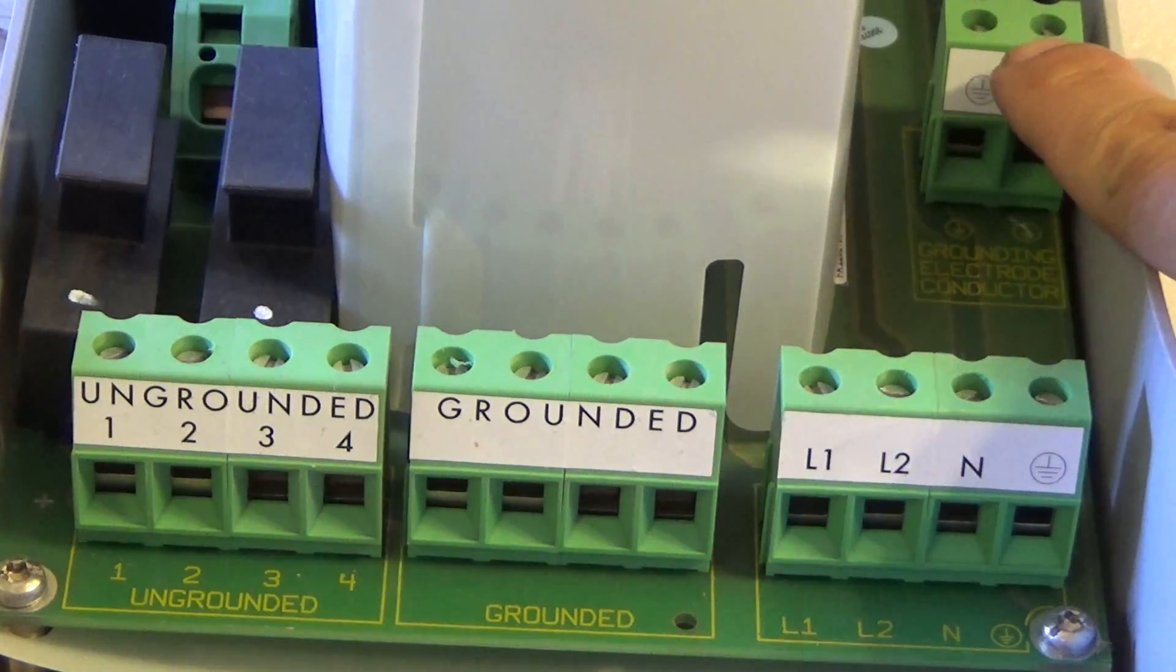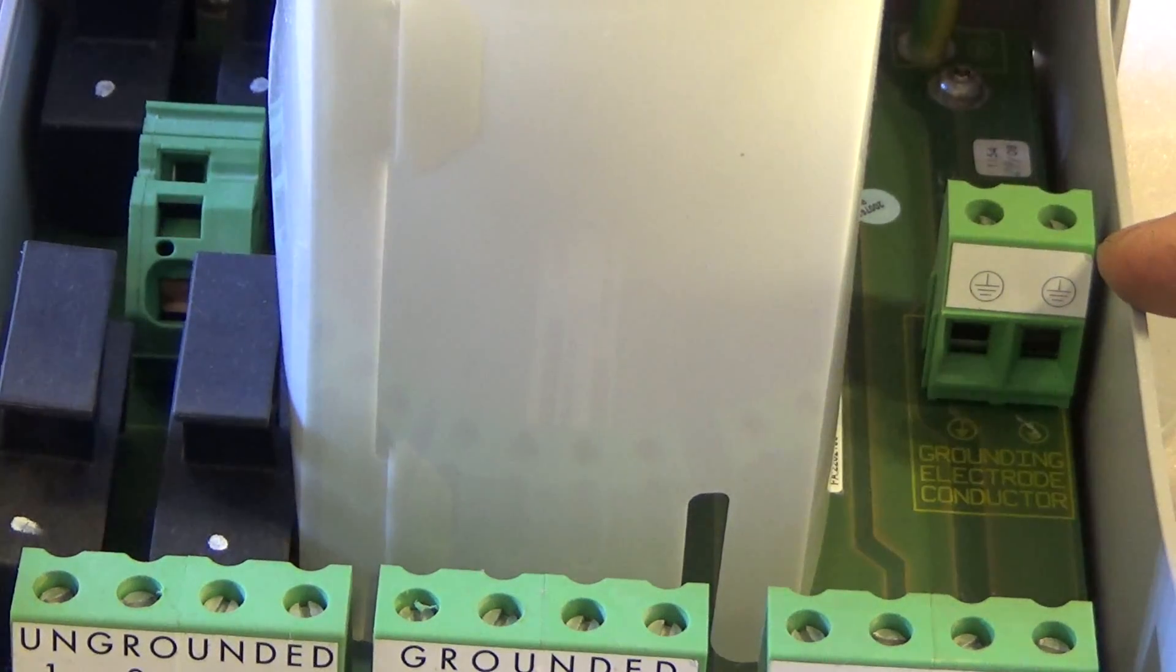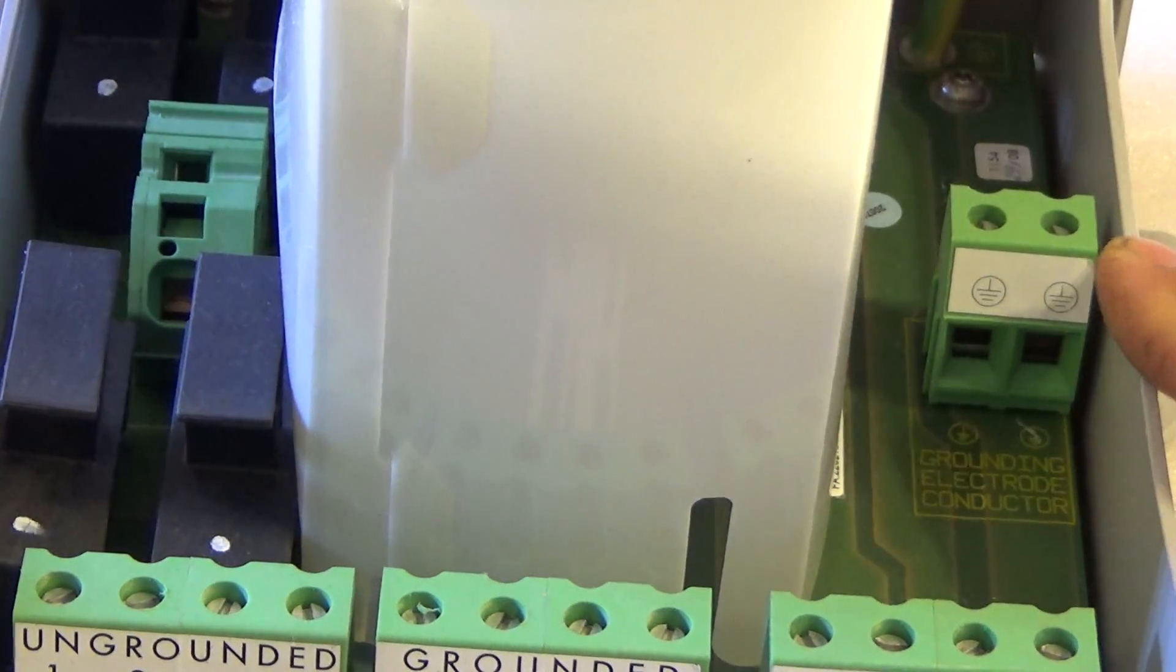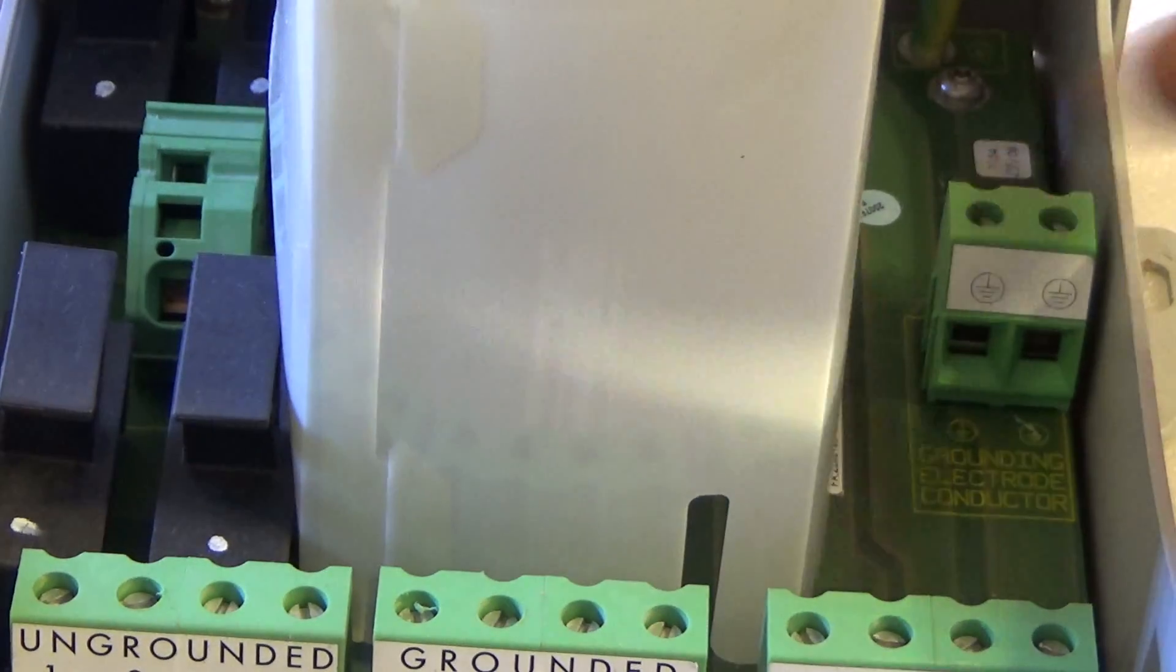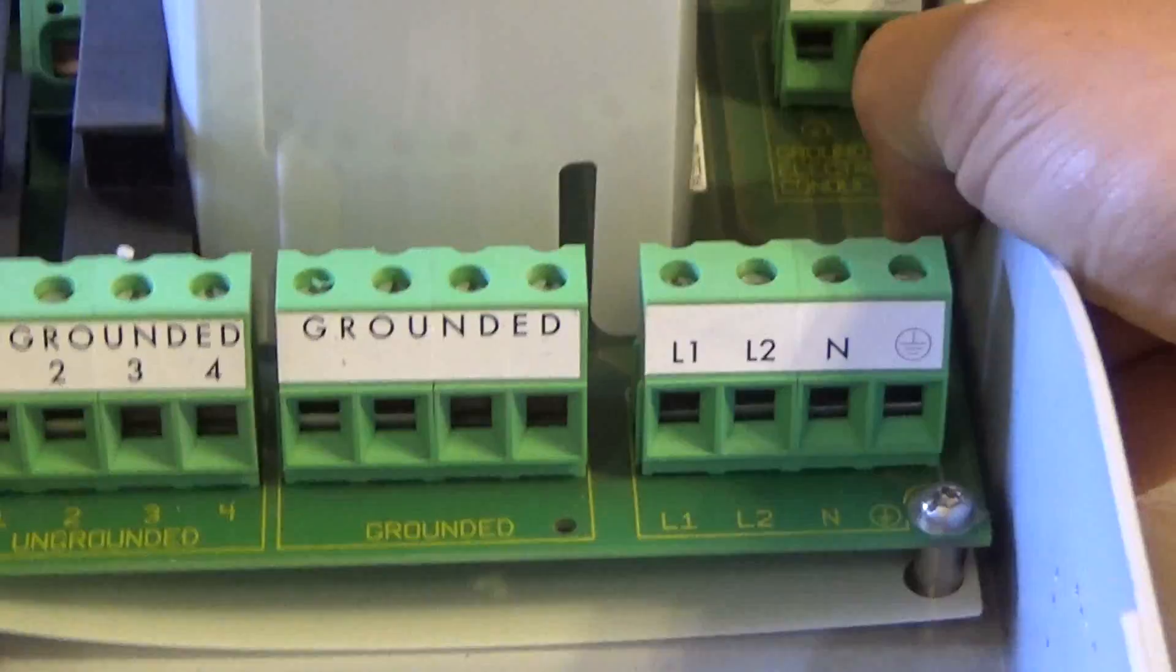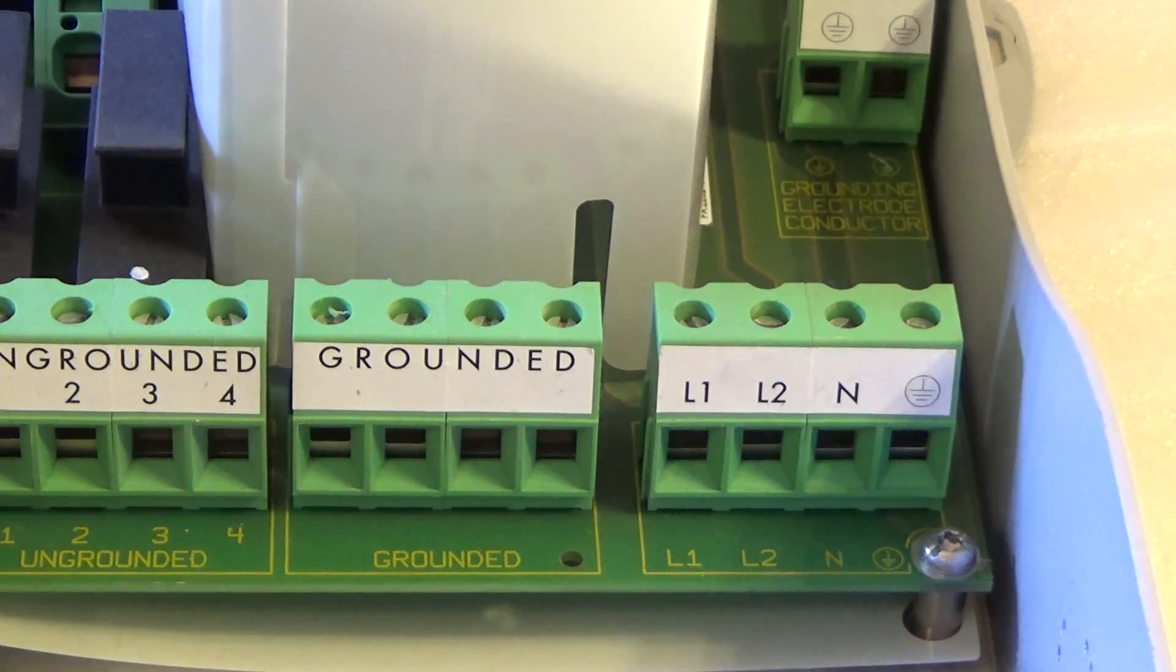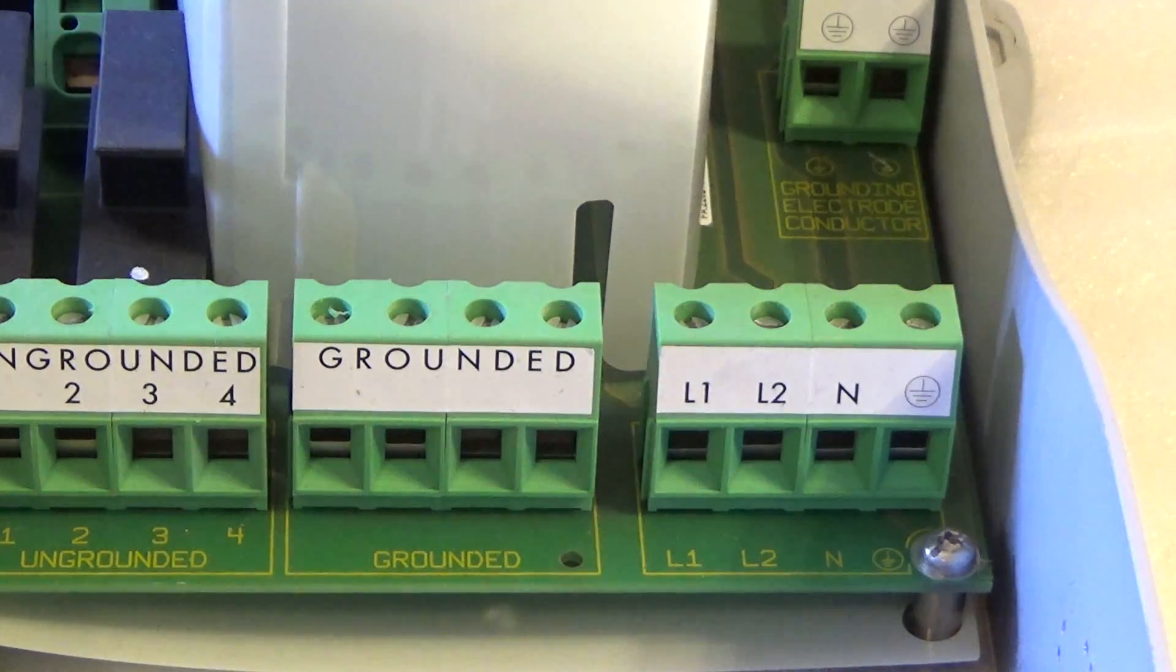On the top here, we also have another connection for ground. It's called ground electrode conductor. This is when you have an electrode that is pounded on the ground that you want to connect directly onto this. But usually, I don't really need to connect to this. All I have to do is connect to ground over here and that should be fine.